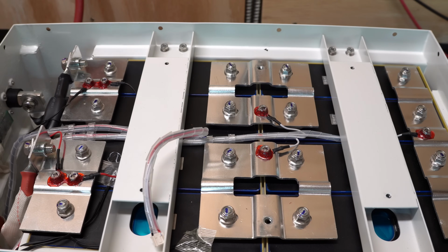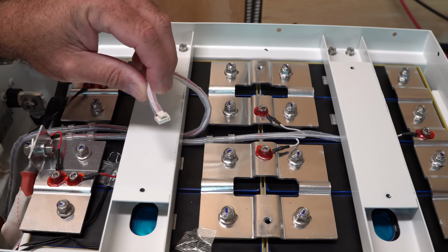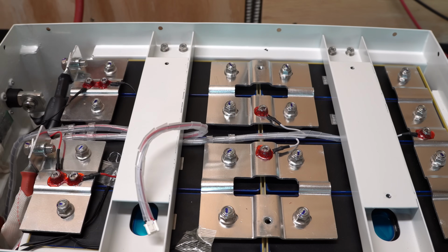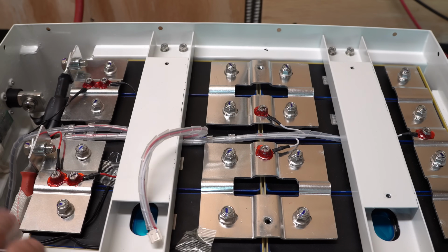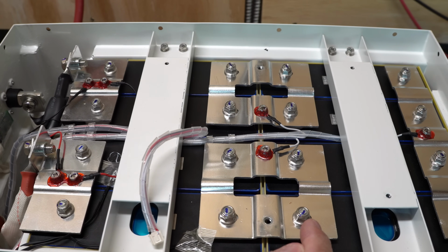Now, while we've got the lid off, let's just take another quick look in here. This is the lead for the display on the top of the lid, but they've got bus bars in here that are nice quality. They're actually not welded - they're bolted with Loctite, and it looks like they have little checks on them with a marker that say, I assume, quality control checked each one for torque. That's what I would assume those marks are for.